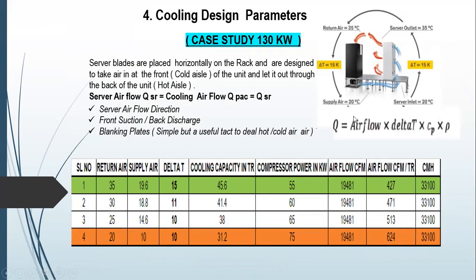As we get into the next slide, this is the CRAC unit. These are the racks. The servers are placed horizontally. Again, it is very important to understand what type of server it is, whether the servers take the cold air from the bottom or are vertical. It is very important to check that the servers are placed horizontally, so that the cold air goes to the front of it and the hot air goes out behind. In the sense, you have a hot air and a cold air containment. It is very important to check what type of server it is and where the fans are located.